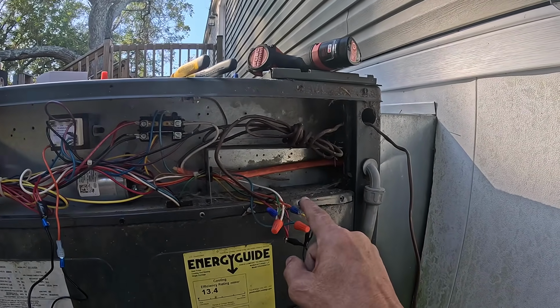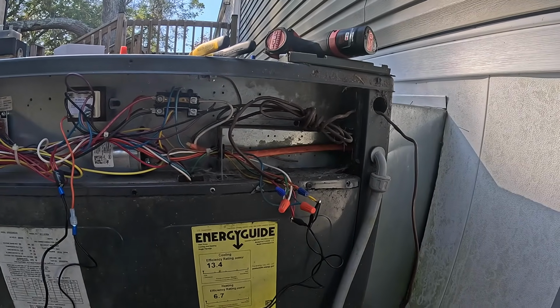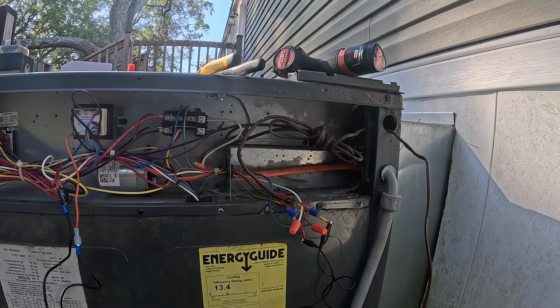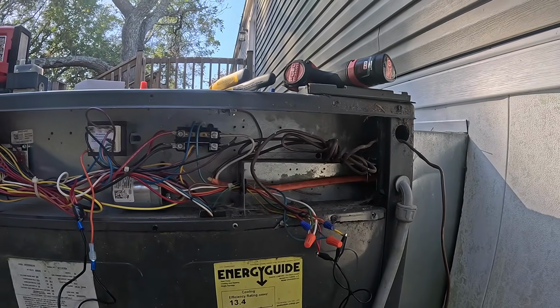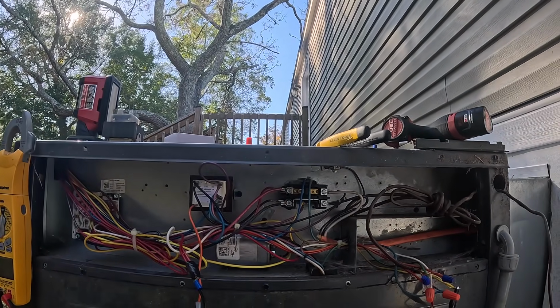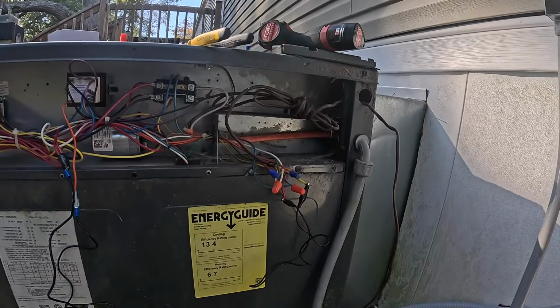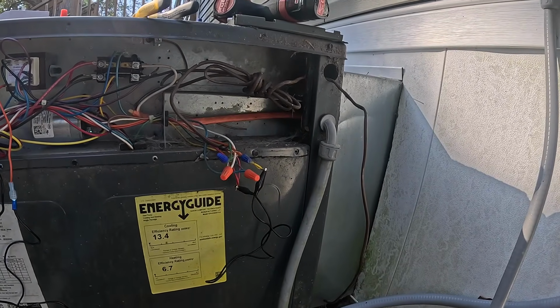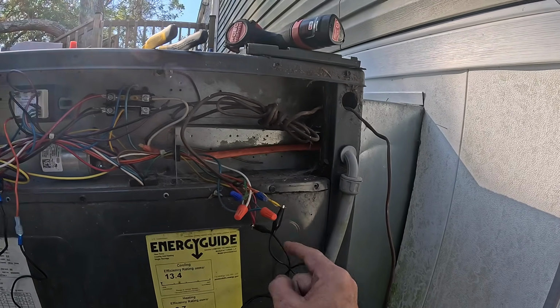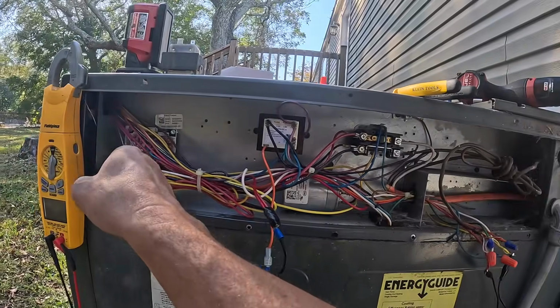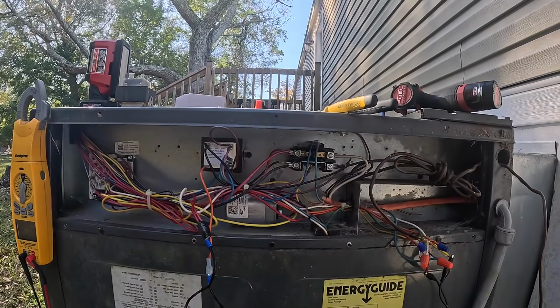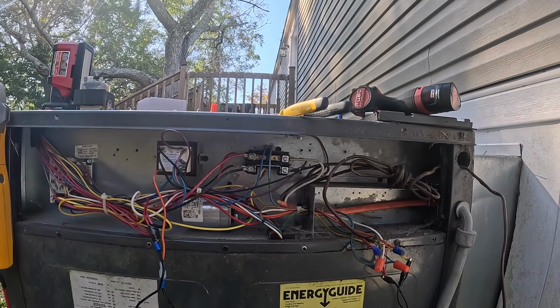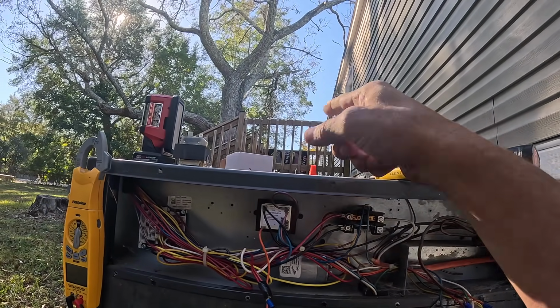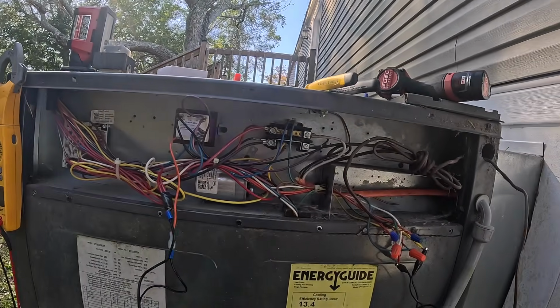Okay, because I haven't jumped out to orange, this is now running in heat. When I jump to Y, that normally goes through this defrost control board and to my contactor. It also goes through any pressure switches I may have.